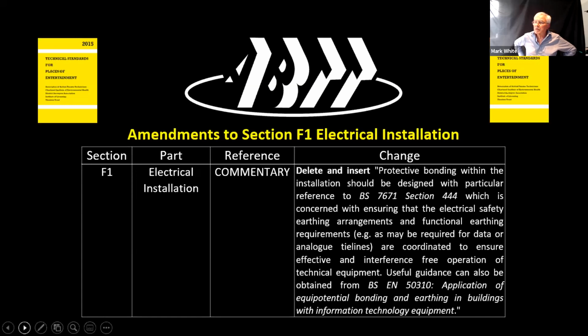And yes, it's now the protective bonding. As those of you familiar with BS 7671 will know, there are various changes in the nomenclature for bonding. We're still trying to maintain an earth equipotential bonding zone for all of our equipment, but this basically says that these days... we'll go back, we're about to appear, this is the second section, where we talk about the old days of having technical earths. Well, the old days of technical earths have gone. This was always to do with analog equipment, because you could set up earth loop hums and various other things.